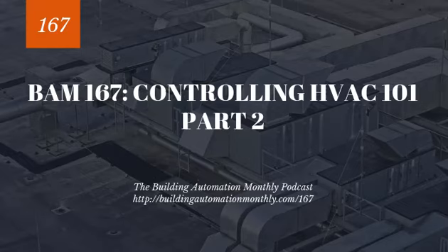Not only is it inefficient, but just like your car or any other motor, every time you turn it on, that's some wear and tear. And so if you're cycling it on and off, you're going to shorten the life cycle. So that's where you tend to see a 5-minute minimum on and 5-minute minimum off. And you tend to see thresholds at which you'll engage your DX compressors or your strip heat, etc. So from there, right, now we move into looking at 100% outdoor air units.